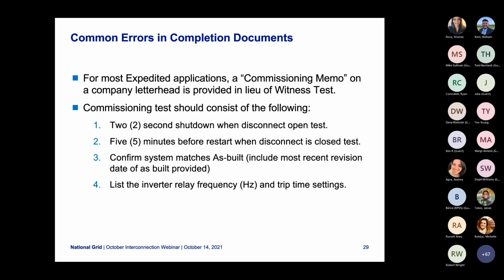The common errors in completion documents. For most expedited applications, a commissioning memo on company letterhead is provided in lieu of the witness test. The commissioning memo should consist of the following: the 2-second shutdown when the disconnect is open test, as well as 5 minutes before restart when the disconnect is closed test. We have to confirm that the system matches the as-built.